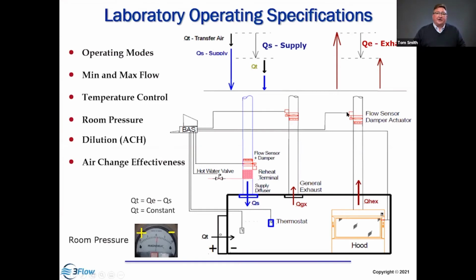So looking at the hood, we talked about the min-max flow for the hood, but we also have to match it to the supply in the lab. So what is the balance: how much flow is going out of the hood, how much air supply is coming in, what is the isolation or pressurization required to provide the appropriate pressurization for the space, and how much flow is required for temperature control. So the thermostat responding to the general exhaust, modulating to provide the right supply. And so all of these things are working together. We can't have one independent of the other because they all influence the air balance. And then what's the magnitude of the airflow from an air change per hour perspective? So these are all factors that need to be taken into account, and we're going to go through the measurement techniques to evaluate.